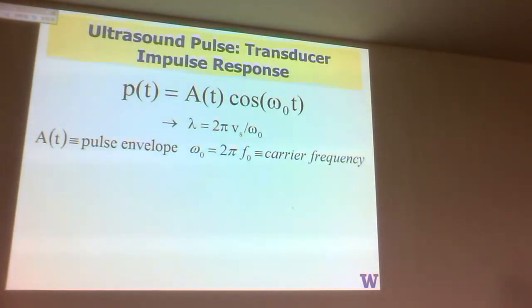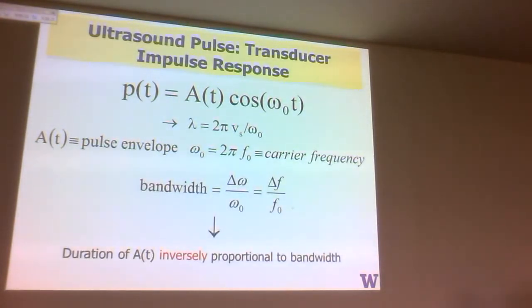From that, you have the Fourier transform of just the pulse itself. It's very broadband, 50% or more. Okay? So, the pulse that you put out for this pulse echo can be described in the simplest way as an envelope and a carrier. So you have the envelope A of t, be something like a Gaussian, which we typically use just like in optics. Spatially, you use a Gaussian. Here, temporally, we tend to use a Gaussian. And you have a carrier, cosine omega 0 t. And when we say we're imaging at 50 megahertz, we're imaging at 2 megahertz, we're imaging at 14 megahertz, that's the carrier frequency. Because the carrier frequency determines the wavelength, and you'll see how that comes into play in the rest of the imaging system.